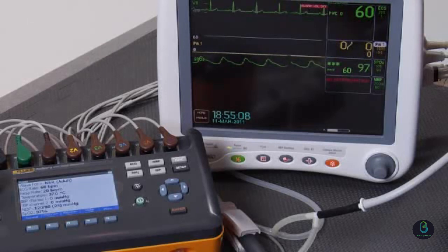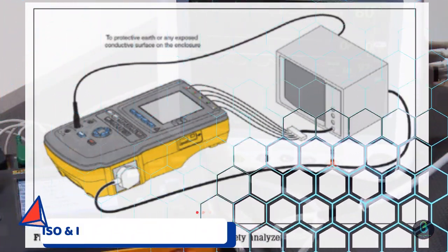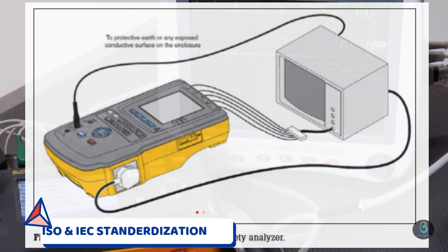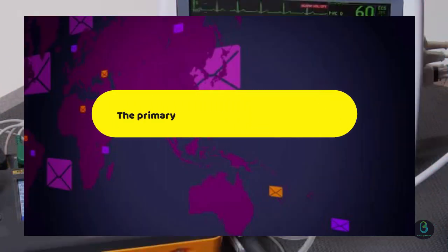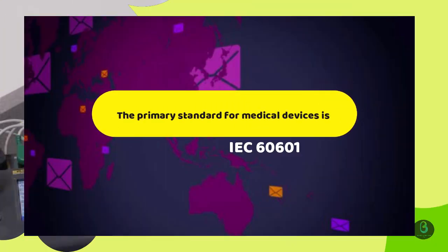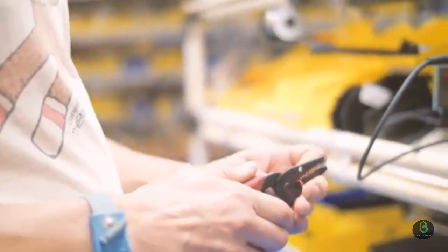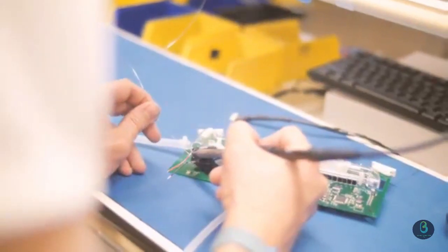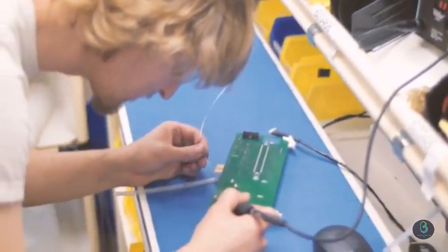There are General and Specific Standards for Medical Device Electrical Safety. The primary standard for medical devices is IEC 60601. General requirements for protection against electric shock hazards are covered in IEC 60601.